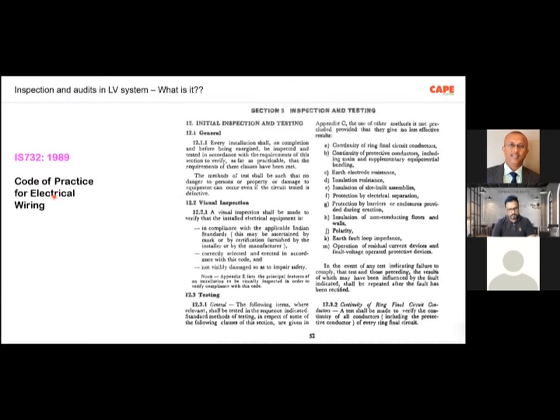A properly designed, erected and tested electrical installation shall ensure that in case of an overload, your device should trip. In case of a bad device, your protective device should trip. In case of a loose contact, your device should trip. Before it makes a fire, the protective devices are supposed to operate and disconnect the supply. And that is why it is the measure against fire and electrocution.